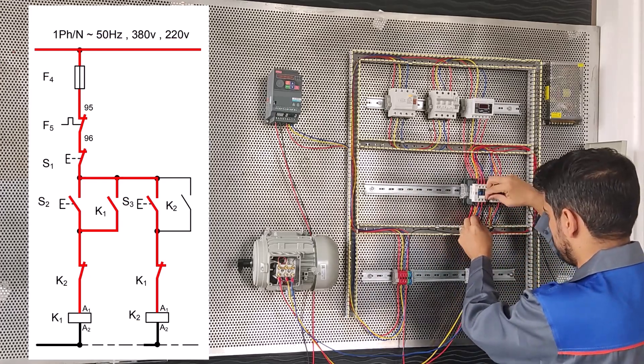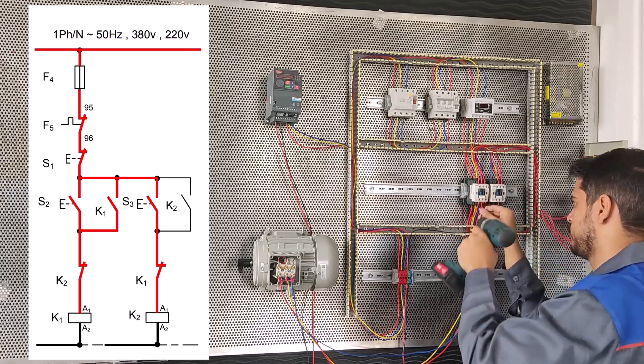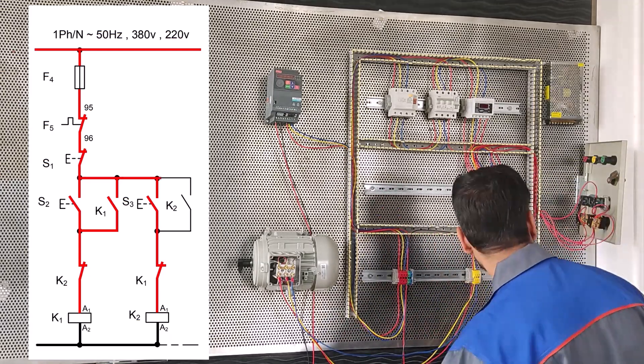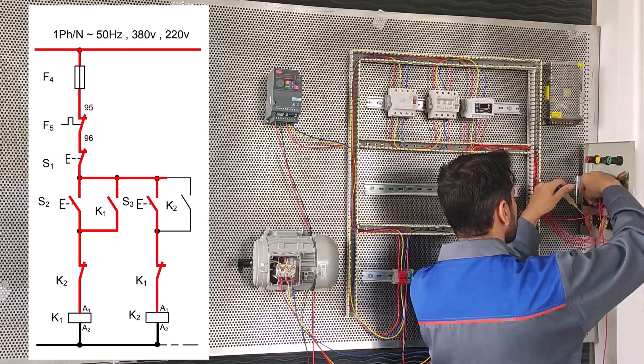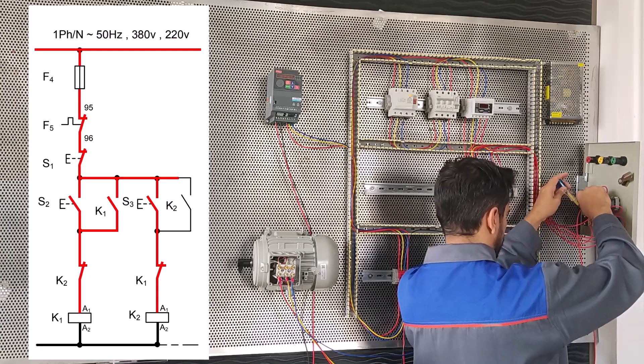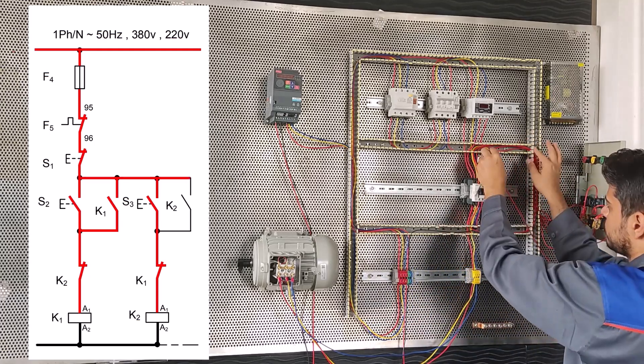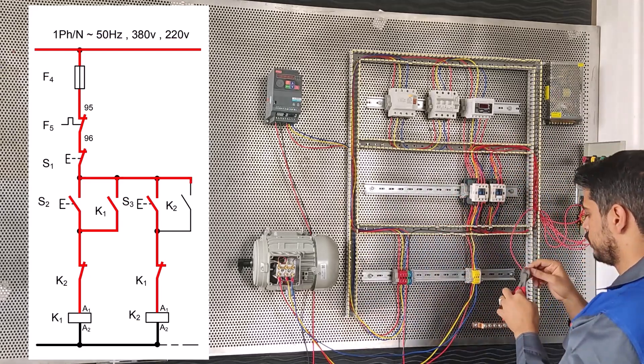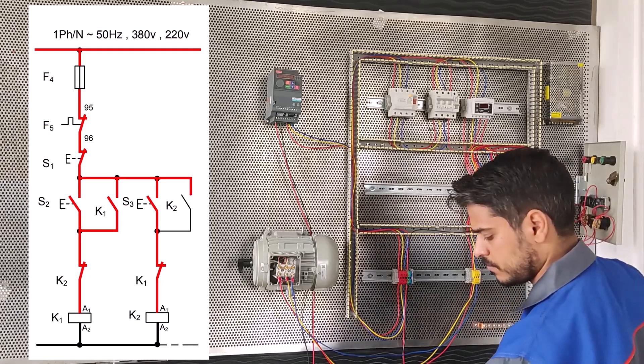And A2, we connect contactor K2 to zero. At the end, we parallel 13 and 14 K2 conductors with 13 and 14 starter S3. We connect from 13 starter S3 to 13 contactor K2. After 14 contactor K2, we connect to 14 starter S3.